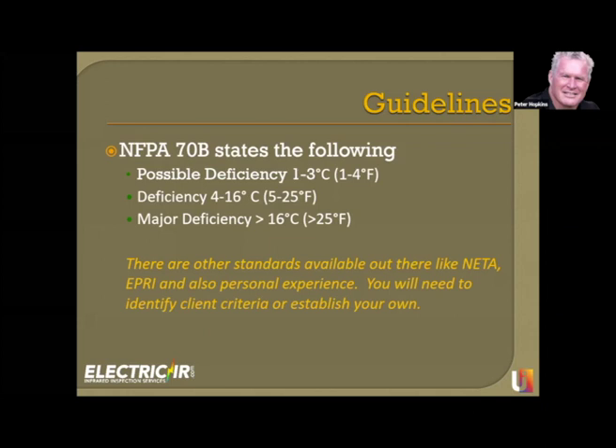I had a university where I was doing the survey, and I found a 300 degree fault on an automatic transfer switch. I said this is a major fault - you could hear it buzzing inside. You didn't physically see it, but the thermal image was glowing.